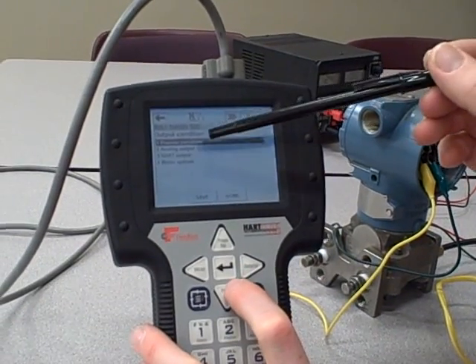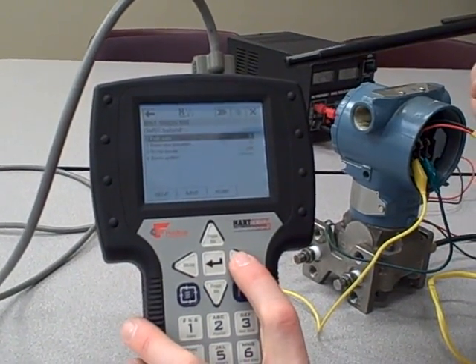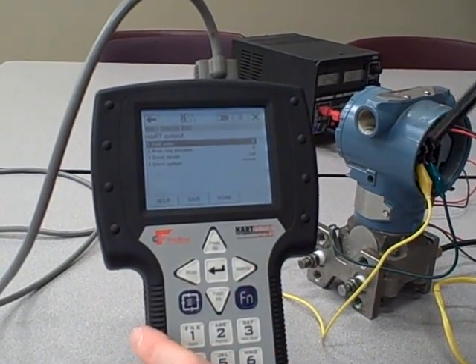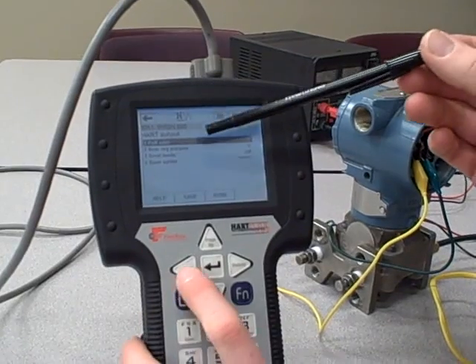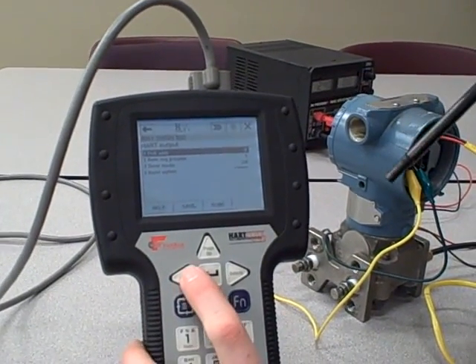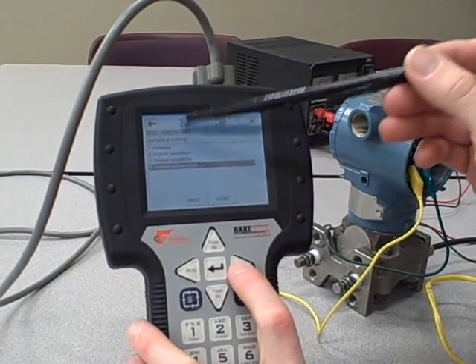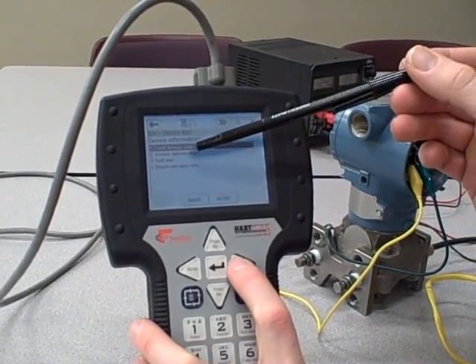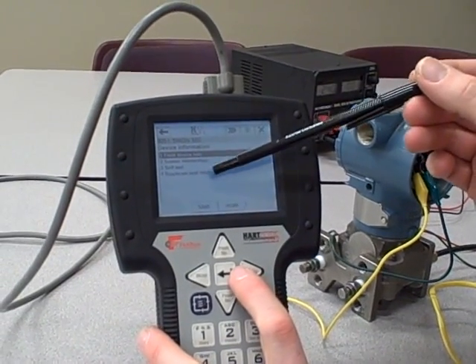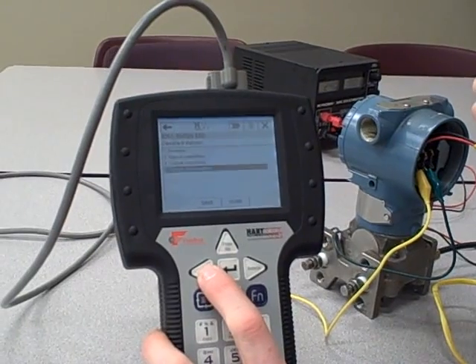We can also go into Output Condition and configure some things regarding the Analog Output. The HART Output, for example, what variables are output by the HART Protocol. The Burst Mode, for example, Poll Address in case it was a multi-drop transmitter. All kinds of things here. And then under Detailed Setup, we also have Device Information. We can program information about self-testing, whether or not it has diaphragm seals, information about the sensor and the materials it's made out of, things like that.